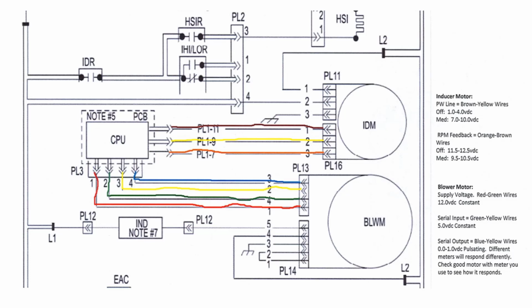The IDM, or the inducer motor, is also an ECM motor, and it has a PW line, the brown and yellow wires, which in the off cycle you will read 1 to 4.0 volts DC, and when the inducer is running at medium, you will see 7 to 10 volts DC. It also has an RPM feedback line, which communicates back to the board the RPM of the inducer motor. This is the orange and brown wire in this case. And in the off cycle, you'll see 11.5 to 12.5 volts DC.